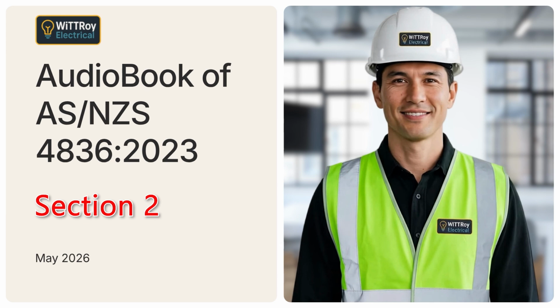PPE means personal protective equipment. This clause also explains that protective devices may not always operate fast enough to protect the worker during an arc fault. That is a key safety point. Do not assume that a circuit breaker or fuse will always protect a person from arc flash injury. The arc fault current may be lower than the bolted short circuit current, and the protective device may not operate quickly enough. For high current equipment, especially equipment rated at 800 amps and above, an arc fault study should be completed as part of the hazard identification and control process.